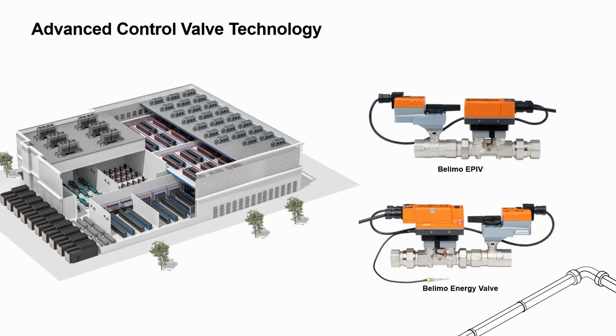The advanced control valve technology from Belimo is vast for your liquid cooling applications. The Belimo EPIV is our flow control valve. That's our electronic pressure independent valve. It's networkable, the flows are changeable, and it provides particularly excellent flow control capabilities. The energy valve is just kind of like its big brother. It still does all the same things, but it's a fully integrated BTU meter. It allows us to measure all of those values. It allows us to do differential pressure control and allows us IP connections as well.